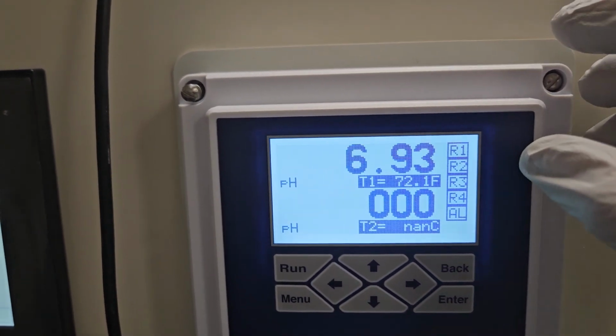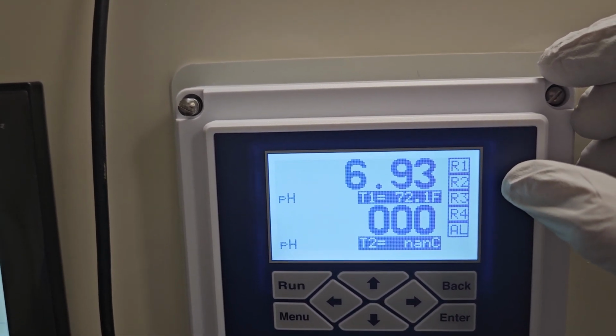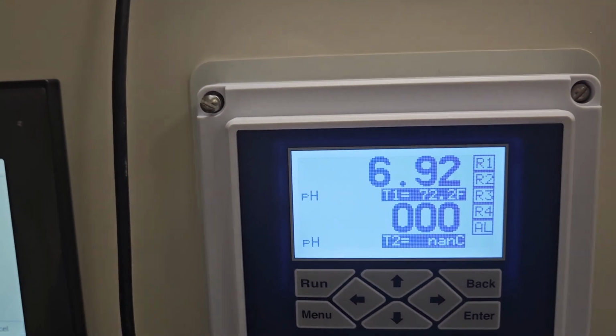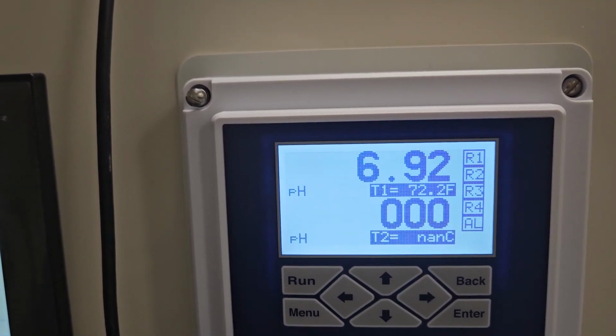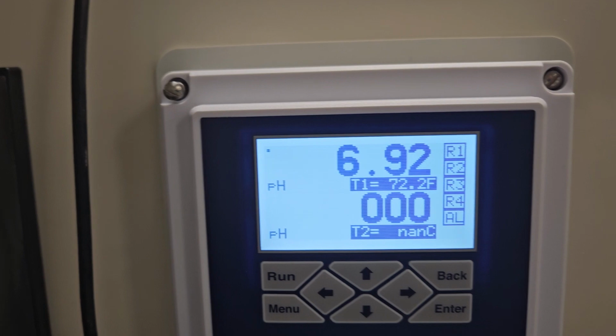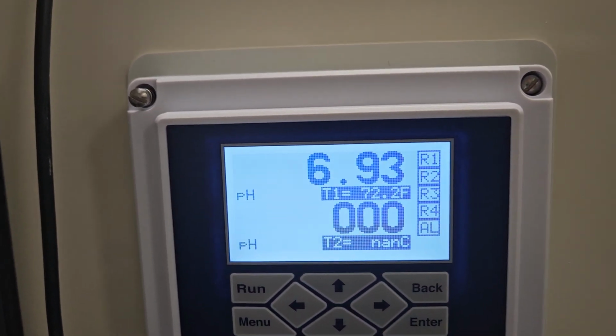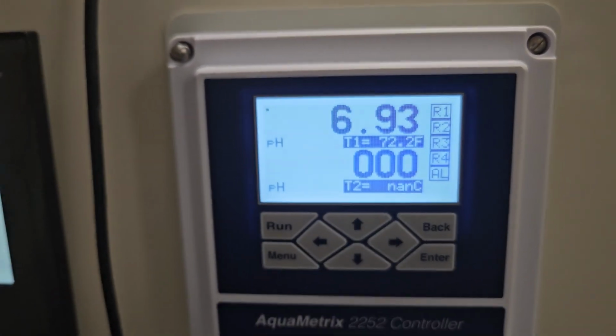I believe relay 2 is the acid or coagulant feed, and I had that set at a much higher limit to go on, so it hasn't gone high enough to activate the on of the acid relay, which is 2. Hope that helps.